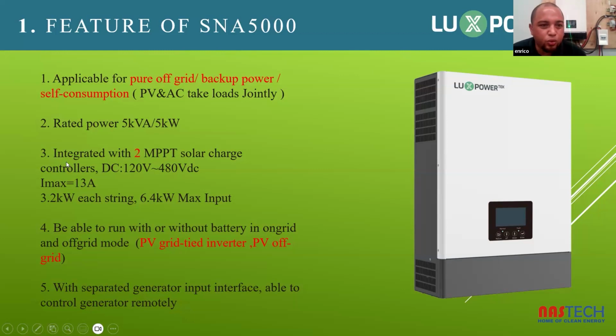The inverter has two dual MPPT solar charge controllers. When you look at the manual, you will notice that it says SNA 5000 WPV. That means wide photovoltaic voltage. So we have a very wide photovoltaic voltage ranging from 120 volts to 480 volts DC. The max input current is 13 A per string, there is a maximum of 3.2 kVA, and together the total wattage is 6.4.